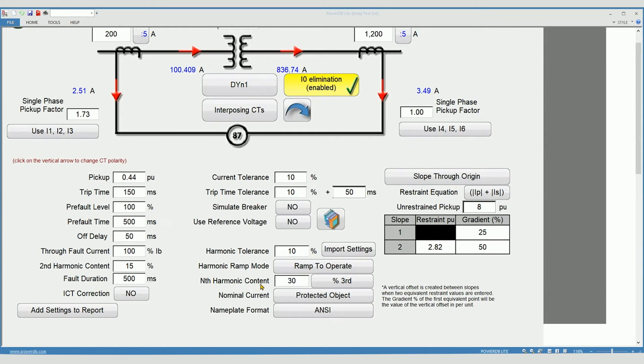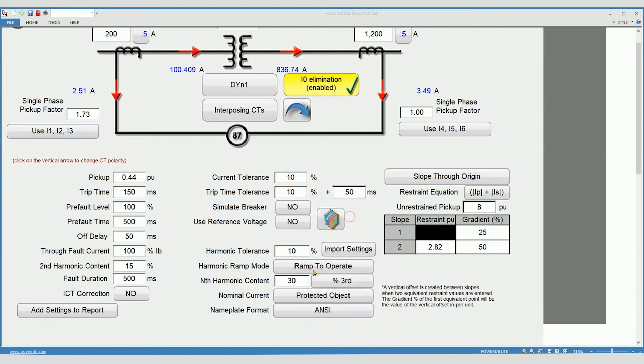Nth harmonic content. Most modern relays allow for multiple orders of harmonic content for restraint and blocking. Enter the order harmonic your relay requires and the related setting.